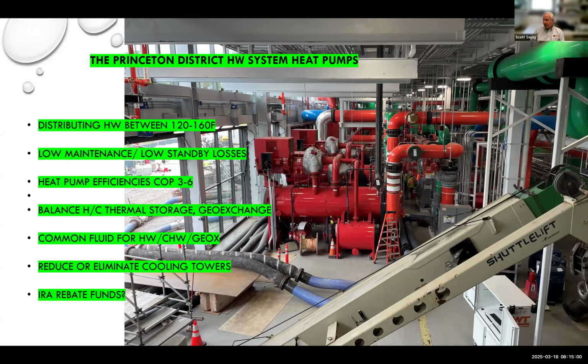Now, each building that we convert off of this plant results in a 65% reduction in CO2 consumed because of the cogeneration efficiency, which is not going to get any better, as I said, and the heat pump COP. And each building converted so far has resulted in roughly 28% reduction in operating cost. The shoulder seasons have the highest COPs, where you can balance heating and cooling loads, and you don't have to use the field or the tanks.